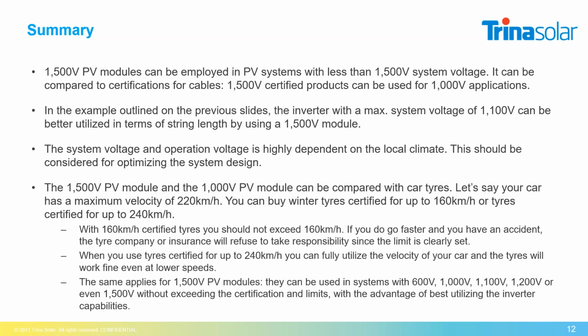For example, we also know it from the cables. There was a change in terms of standardization for the cables here in Europe, and according to the new standards, all cables for PV applications are certified for 1500 volts. In the past, it was also 1000 volt and 1500 volt. That means if you have a system with 900 volts, you can always use a 1500 volt cable. If you have a voltage level on a cable of, let's say, 1020 volts, you have to use the 1500 volt cable. That means the 1500 volt cable can be used in any case, but the 1000 volt not in all cases. The same applies for modules to be within the standardizations.